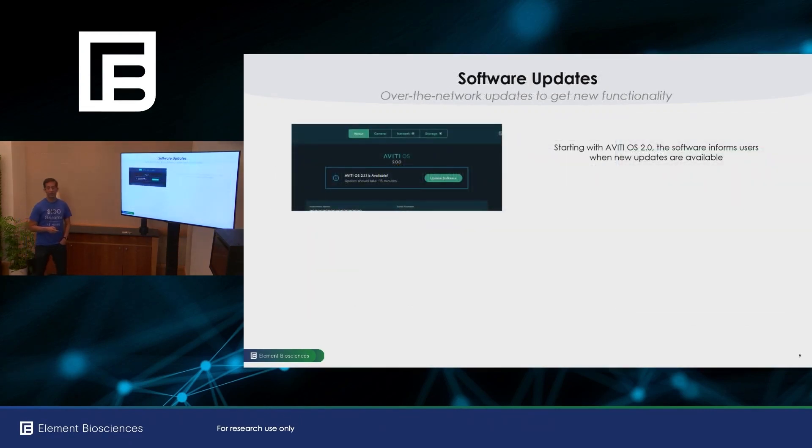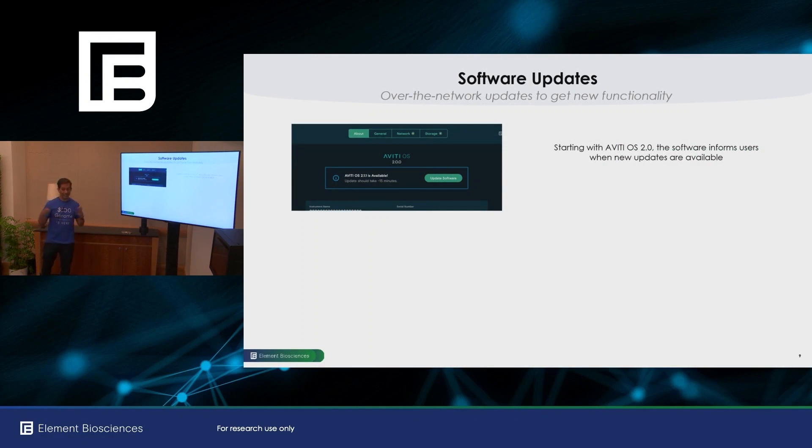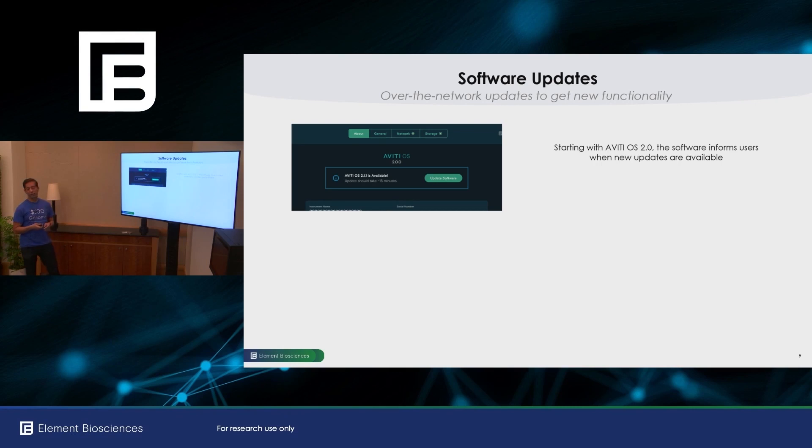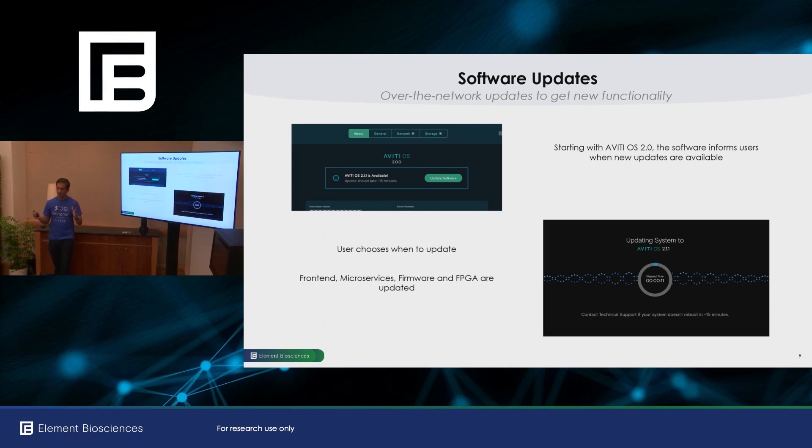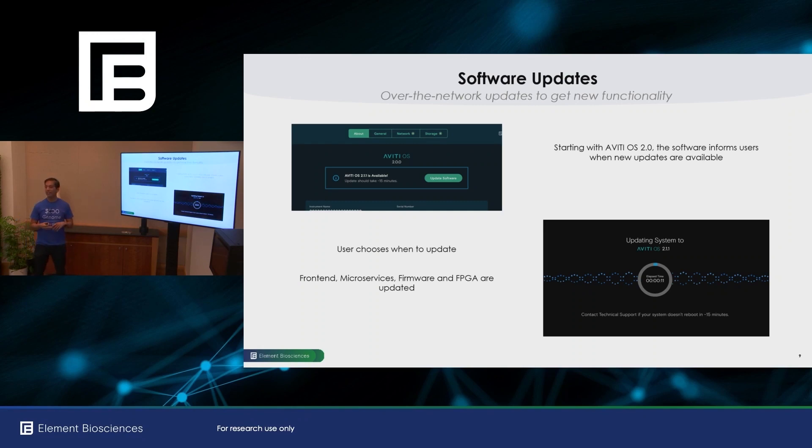Another new feature in Aviti OS 2.0 is the ability to get new versions. You're notified when new versions are available, and you can choose to update when you want. So these updates are not just for the front-end user interface, but also for the back-end microservices, the firmware, and even the FPGA can be reflashed.